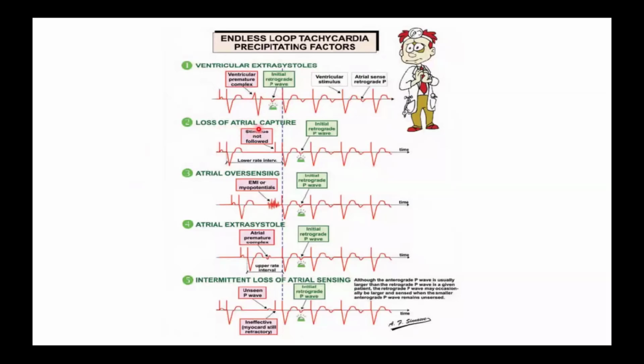Or it may be initiated by atrial loss of capture. Here, atrial pacing, no P wave, then V pacing, then retrograde conduction, as the atrium is not depolarized, and a retrograde P wave is noticed and starts PMT. Or atrial oversensing, which starts a sensed AV interval followed by ventricular pacing, and the atrium also is not depolarized. Also, an atrial extrasystole at the upper rate interval may be conducted at a long AV interval and followed by a P wave.